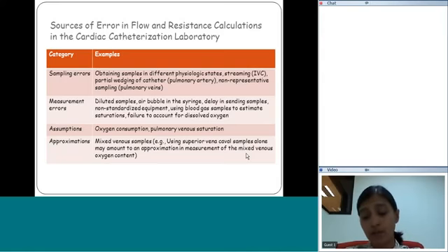I have known cases where this was in an intubated patient and the tube has gone down one lung and one lung is totally collapsed. And when you take an ABG, you notice that the ABG is grossly abnormal. So if your PA pressure is high at that point, it means nothing. So you have to make sure that the respiratory status of the patient is as stable as you can get it to be. The next thing, of course, is your zeroing of equipment. Always make sure you spend the time to zero equipment properly. Now, once you think that you have achieved good zeroing during the course of the cath, make sure that when you enter the ventricle, you check your zero.